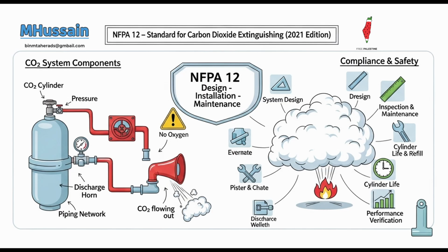Now, the type of fire dictates the exact CO2 quantity needed. For surface fires, like liquids. Yes, those involving flammable liquids and gases like gasoline, propane, or even hydrogen, the quantity is based on average conditions, assuming prompt extinguishment. Okay. The standard provides theoretical minimum CO2 concentrations and then slightly higher design concentrations for a crucial safety margin. Theoretical versus design. Safety factor built in. Precisely. For example, for gasoline, the theoretical minimum concentration for extinguishment is 28% CO2, but the design concentration is specified at 34% to provide that safety buffer. 28 theoretical, 34 design for gas. Right. For highly flammable hydrogen, it's 62% theoretical, and the design concentration jumps to 75%. Wow, 75% for hydrogen. Needs a lot more.